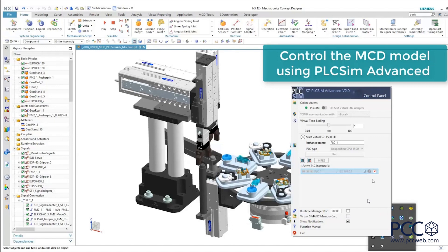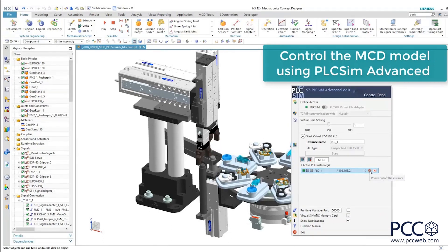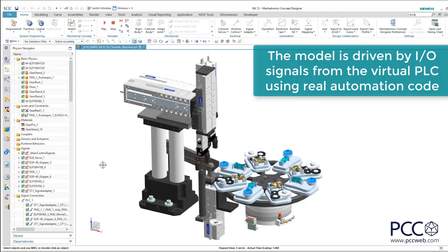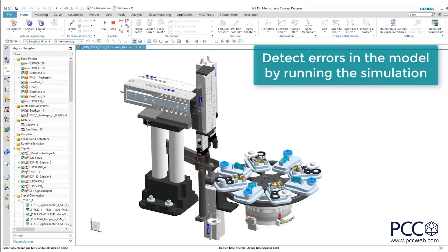What PLC sim Advanced brings to the table is connectivity to the outside world. It has built-in APIs with hooks so that the input and output points programmed in the PLC program can actually interact with the input and output points developed in the 3D model. PLC sim Advanced runs the application in a simulated, software-in-the-loop environment. As you can see, we started the machine and things are happening based on actual PLC logic — not just a standalone model.